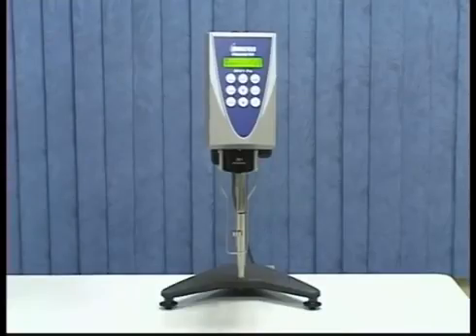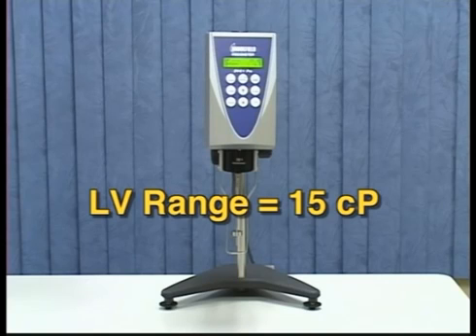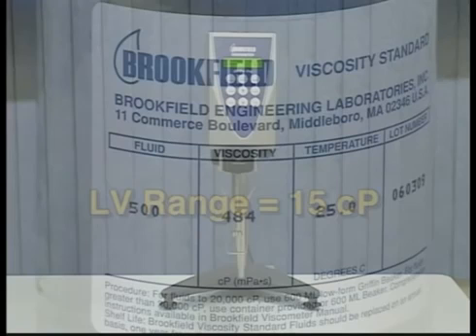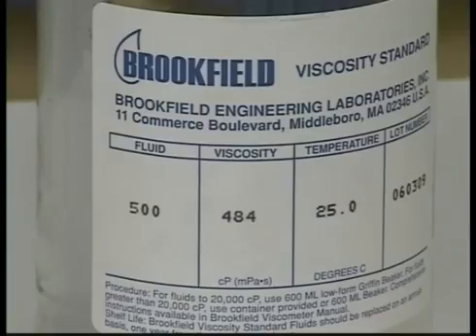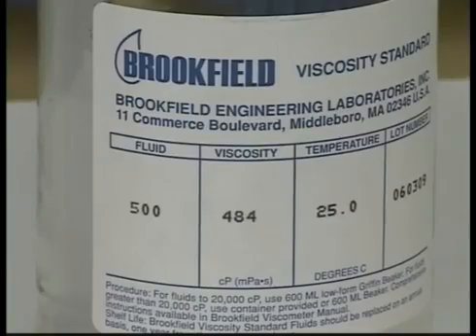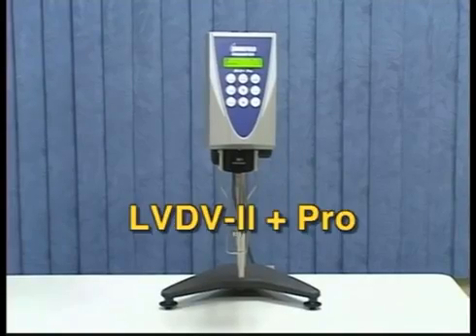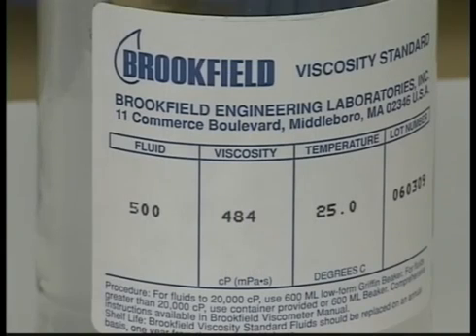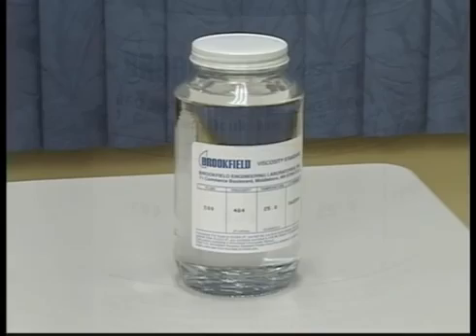Select a viscosity standard fluid based on the torque range of your instrument. For example, an LV torque instrument has a minimum viscosity range of 15 centipoise, so a 500 CPS fluid will be fine. For this calibration example, we will use an LVDV2 Plus Pro viscometer and a 500 centipoise viscosity standard fluid. You do not need to select a standard fluid based on the viscosity value of your material. However, many customers choose to do so as a simple verification.